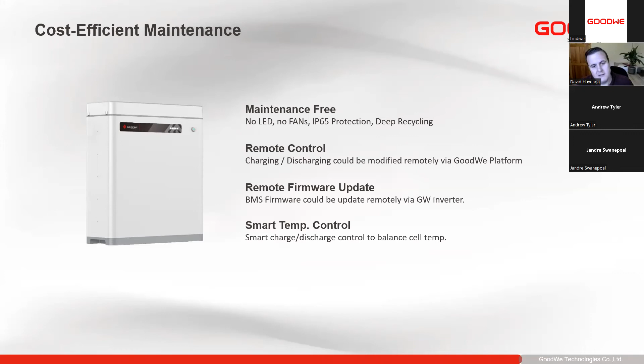And the batteries do have smart temperature control, so smart charging and discharge control based on the cell temperatures. Obviously, if the batteries are very cold, you charge a lot slower to protect the cells, because when it's too cold, that chemical reaction can cause sudden heating of the cell and can cause degradation. So when the batteries are colder, they charge a little bit slower, and as they warm up, they charge faster.